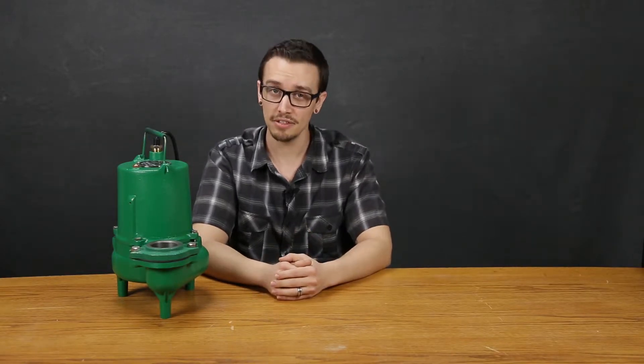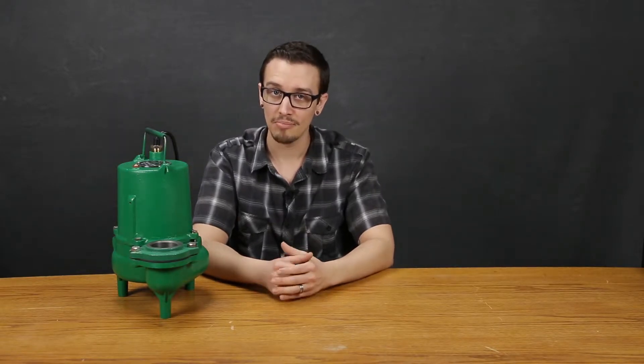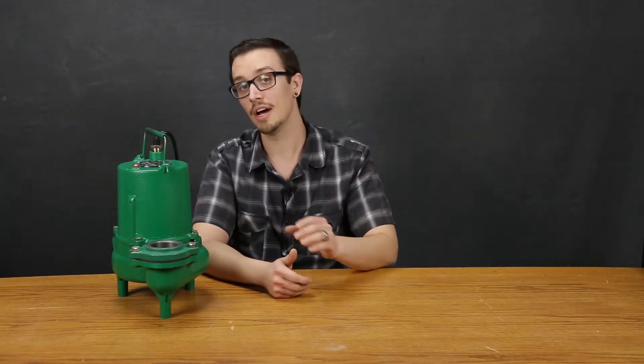This pump comes with stainless steel hardware, a carbon ceramic mechanical shaft seal, and single row ball bearing construction. The cast iron body and oil-filled motor dissipate the heat generated in the motor and help prolong the life of the motor.